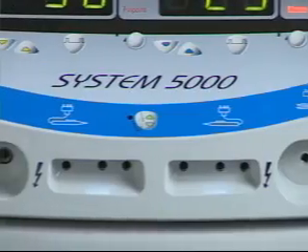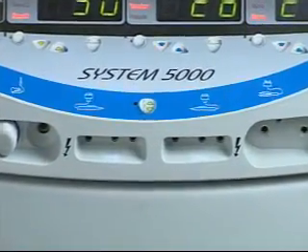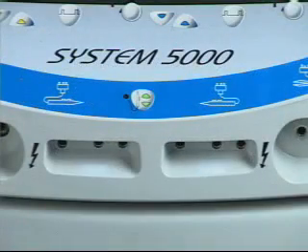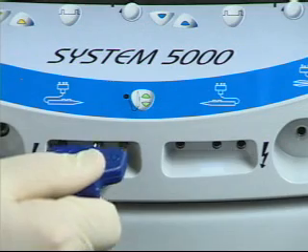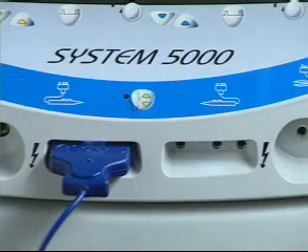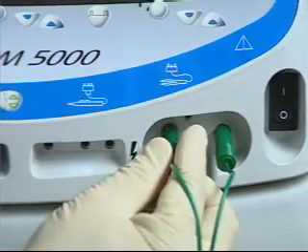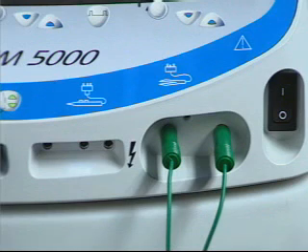Electrosurgical accessories are an important part of the electrosurgical system, as they deliver therapeutic effect and safely remove the electrosurgical energy from the patient's body. Connect the electrosurgical pencil to the generator by inserting the prongs into one of the two illuminated pencil portals. Bipolar forceps cables can be attached in the same manner — simply insert the prongs into the appropriate portal jacks.